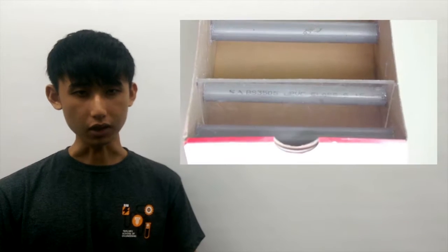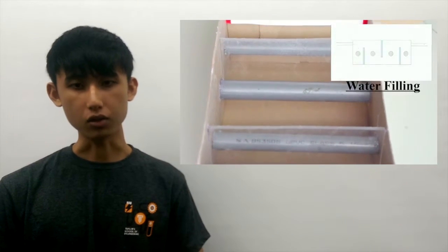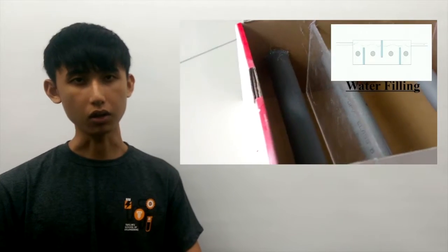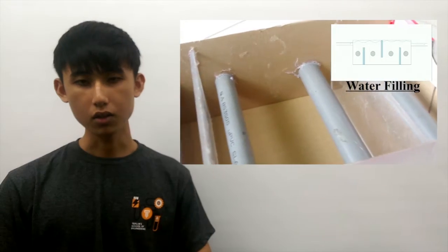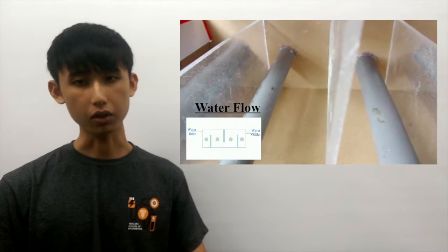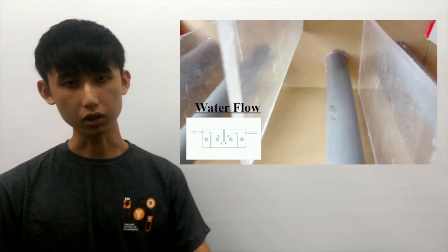This is the design of the inner part of the chiller. The top part is to stop the hotter water from flowing directly to the last section without contacting the PCM. This would happen because, while operating, the hot water from the inlet has low density and therefore will flow to the highest point, so it would move through the chiller from the top part where there is no PCM at all.